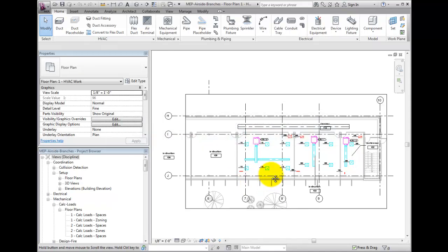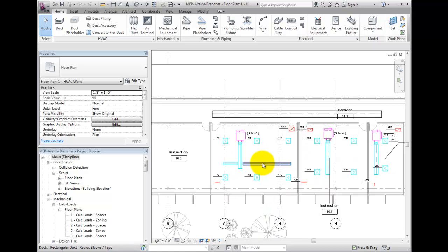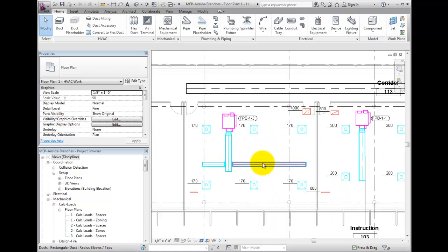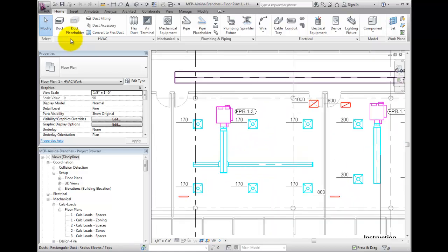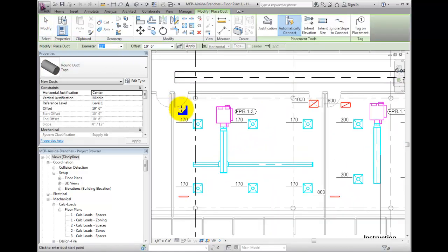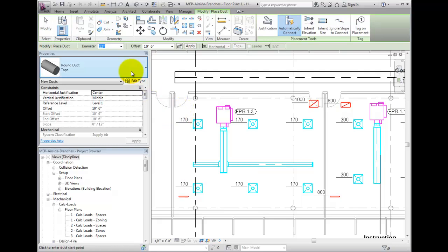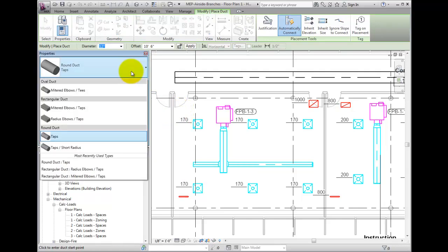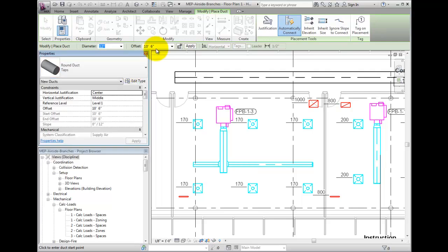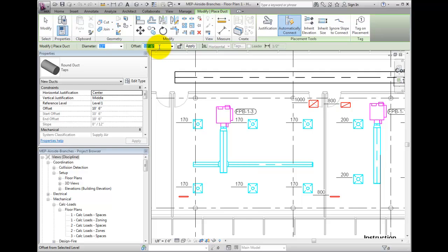Pick the Home tab. Under HVAC, select the duct on the panel. On the type selector, pick Round Duct, Taps. Set the offset to be equal to the offset of the mains, in this case 10 feet 6 inches or 315 centimeters.